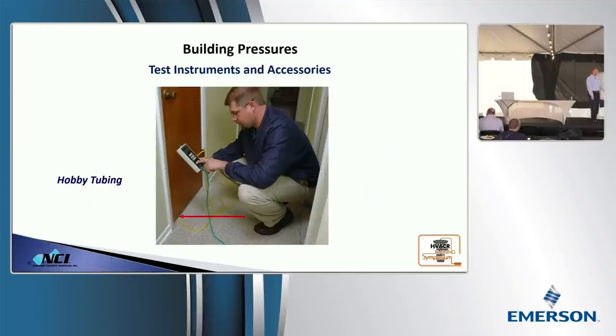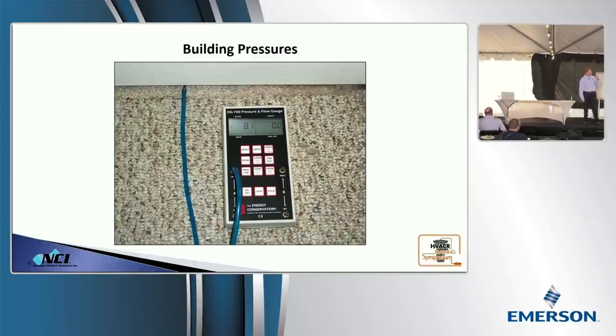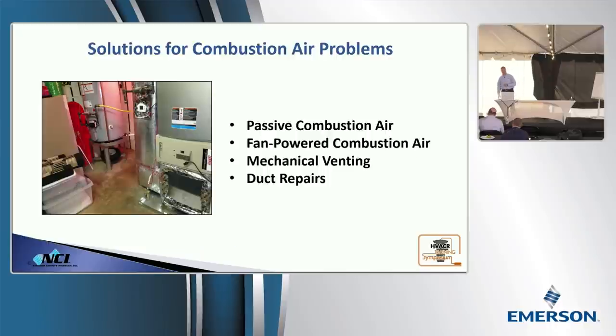So you've got to have some basic stuff. They've got it all across the hall in the booth there. You can see this stuff. On this one, I'm measuring negative 8.1. If you guys can't see that display, negative 8.1 pascals. Is that a good reading or a bad reading? It's a horrible reading. Because that means that room is under what kind of pressure? It's negative, it's in a vacuum. How well is combustion air going to work in that room? It won't. Mechanical rooms should always be under a positive pressure.